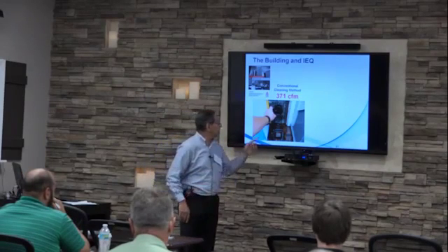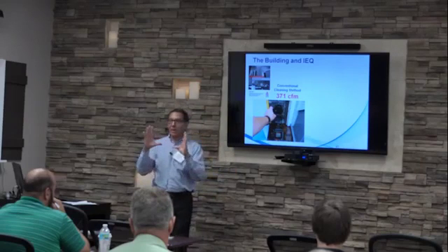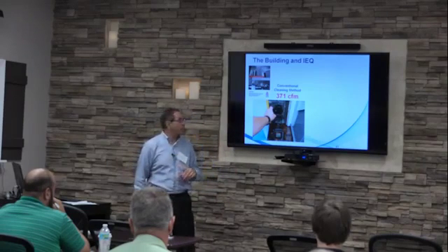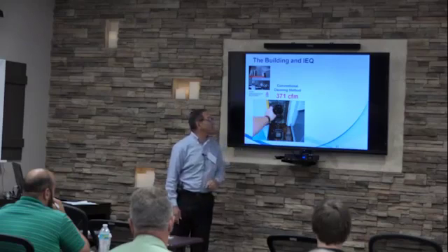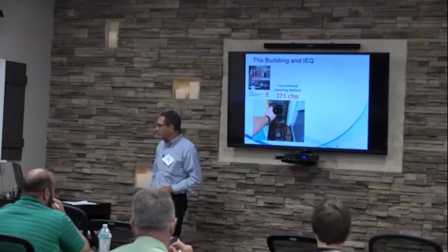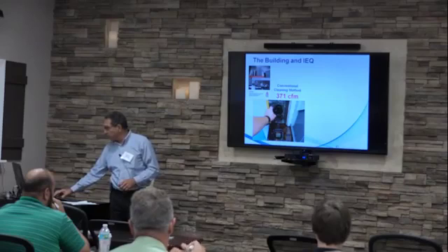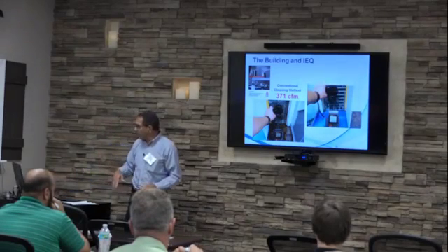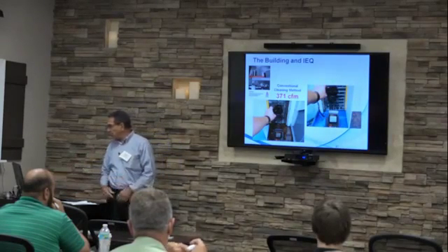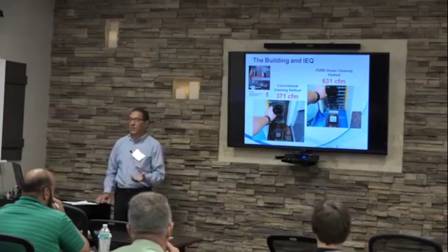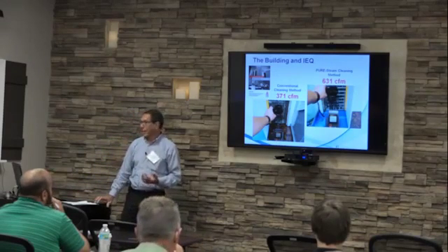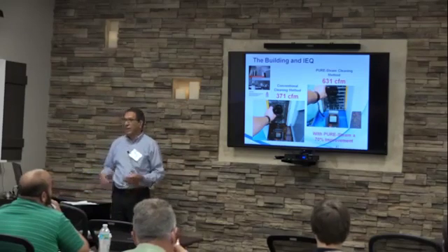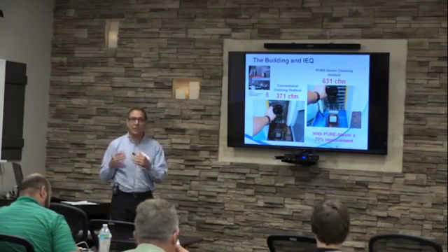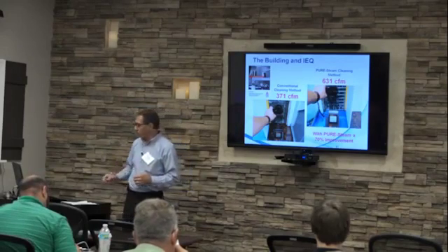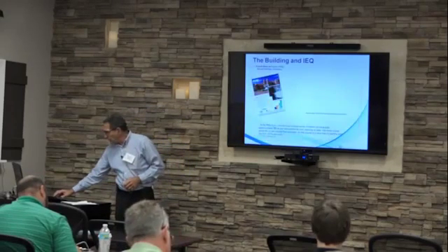The other half we left the way it was - they had tried to clean it but were unsuccessful. We put it inside a cavity with a fan on the other side and measured 371 cubic feet per minute flowing through that coil. After it was cleaned, on the opposite side we measured an increase to 631 CFM. That's a major increase, proving steam cleaning is a much more efficient way of cleaning coils.